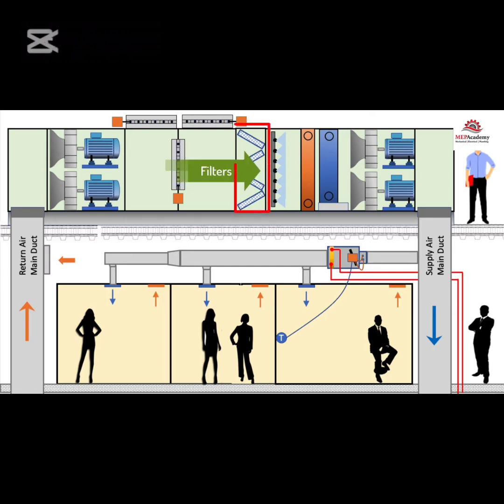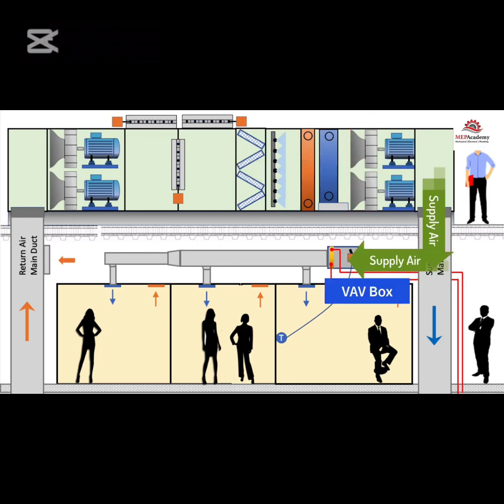Next, the air enters the filter section to clean the air. Various quality of filters can be used depending on the cleanliness requirements of the air. Next, the air travels through a humidifier to add moisture to the airstream before entering the coil section and then through the supply fan that will push the air through the ductwork to the VAV boxes at each zone. The VAV boxes will open and close their damper to satisfy the temperature in this space.